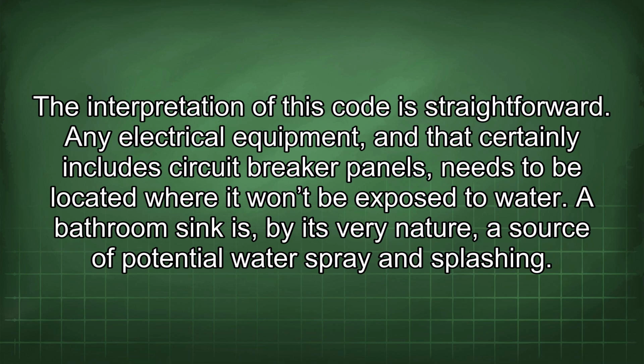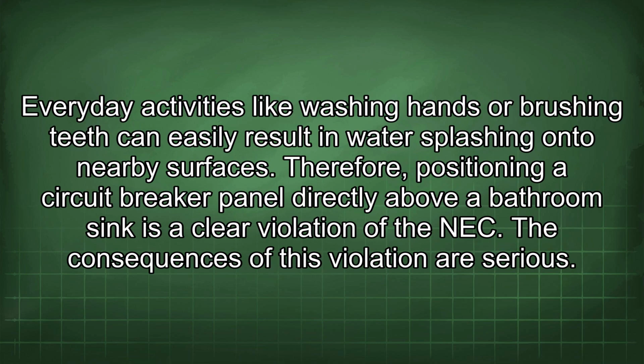Any electrical equipment, and that certainly includes circuit breaker panels, needs to be located where it won't be exposed to water. A bathroom sink is, by its very nature, a source of potential water spray and splashing. Everyday activities like washing hands or brushing teeth can easily result in water splashing onto nearby surfaces. Therefore, positioning a circuit breaker panel directly above a bathroom sink is a clear violation of the NEC.